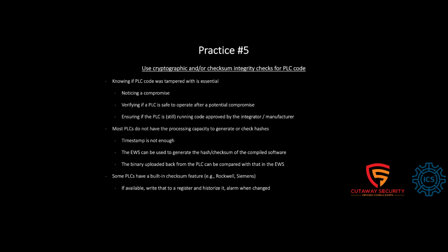But historically, most PLC engineers, such as myself back in the day, would go to the project folder, look at the timestamp and say, yep, that's the last time I edited it. And most people don't enter enough information in that change management software, so you wouldn't even know what changed if something changed. So what we're recommending here is, if the PLC doesn't have any features to generate a hash or a checksum, you can still use the engineering workstation, the EWS, to generate the hash or checksum, and then you can upload the binary back from the PLC to compare. That way, at least you have a clear understanding of what code is in the PLC. Then you can say, okay, this is the same code that we expect to be there.